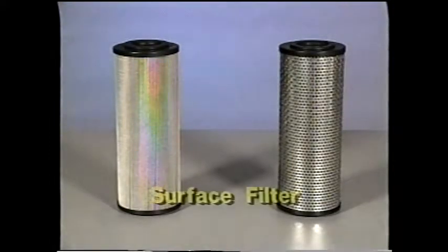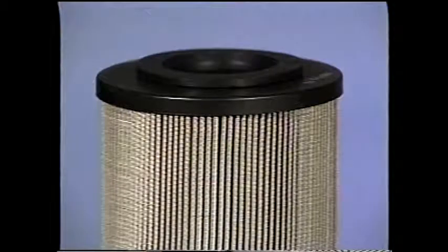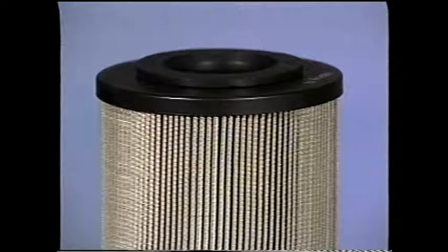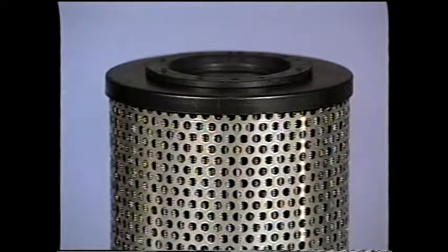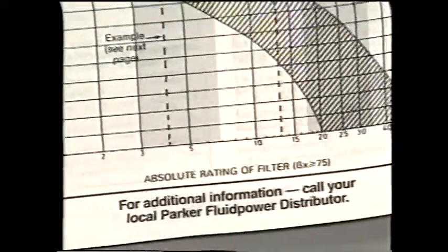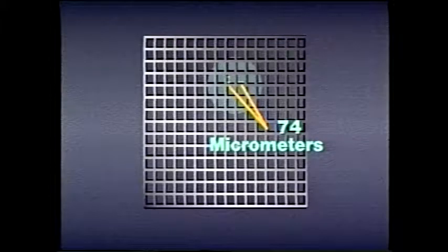The second type of filter, the surface filter, works like a kitchen strainer. It's a wire mesh or perforated metal sheet through which the hydraulic fluid passes. Wire mesh is similar to the screen wire used on your screen door at home, except it's usually made of bronze or stainless steel. Perforated metal is simply a sheet of metal with holes punched through it. Surface filters have absolute ratings which indicate the diameter of the largest round particle which will pass through the filter.